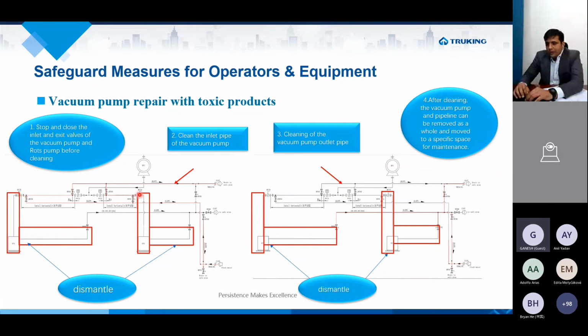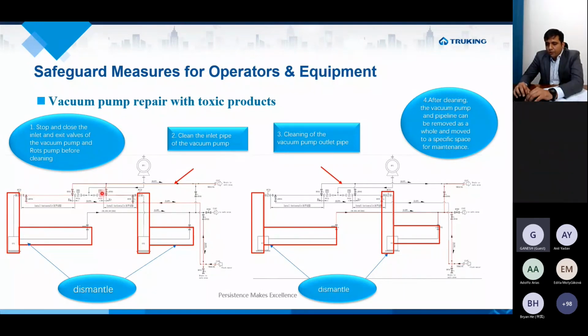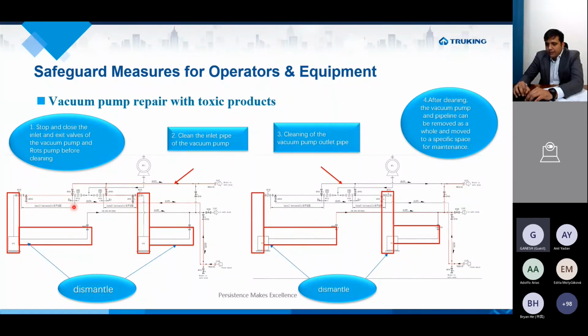And in the second step, we can clean the inlet pipe of the vacuum pump automatically through the CIP/SIP lines. These valves, please note, are closed. The loop is cleaning the complete lines, and the water is going to the drain. In the third step, we clean the vacuum pump outlet pipe. So this is the outlet also. After closing these valves, we can have a CIP done online on these particular pipes.